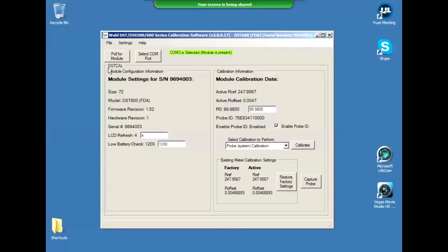So what we have here is the module configuration information, and it gives you the serial number. And right here I'm using DST Cal. Here you can see, it'll tell you the firmware revision in there. The serial number again repeated here. This is LCD refresh, so when we roll over that, it tells you the valid range is 0 to 40 periods of 250 milliseconds. So with a 4 there, that's 4 250 millisecond periods, or 1,000 milliseconds, which is 1 second.